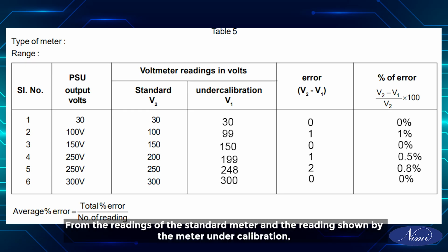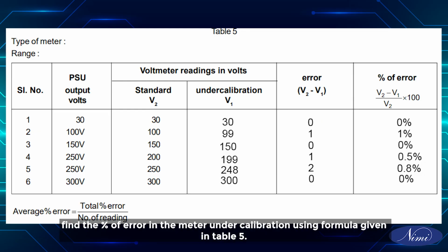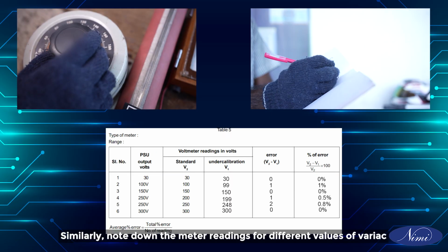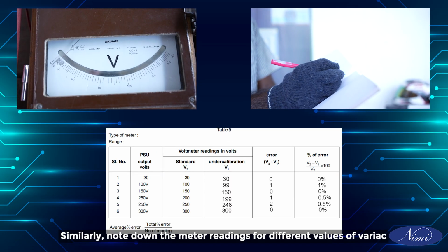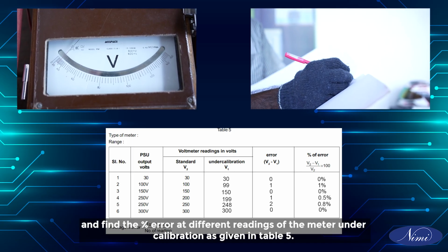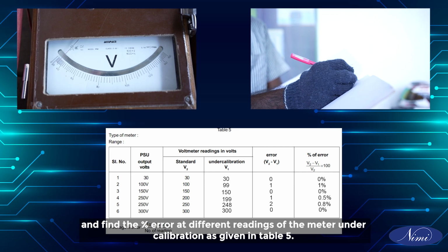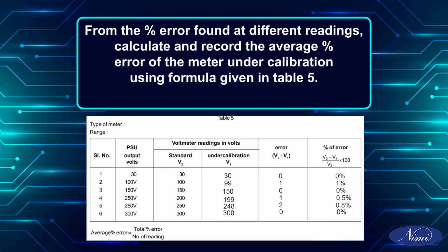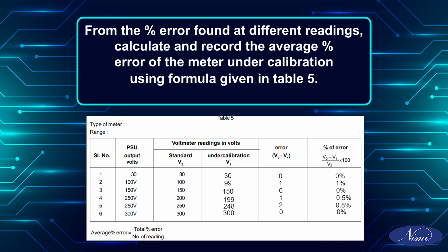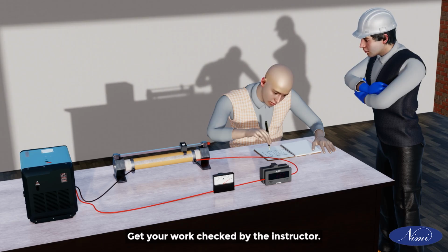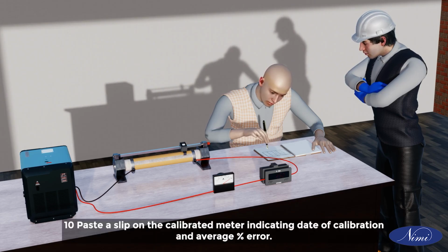From the readings of the standard meter and the reading shown by the meter under calibration, find the percent of error in the meter under calibration using formula given in table 5. Similarly, note down the meter readings for different values of variac and find the percentage error at different readings of the meter under calibration as given in table 5. From the percentage error found at different readings, calculate and record the average percentage error of the meter under calibration using formula given in table 5. Get your work checked by the instructor. Paste a slip on the calibrated meter indicating date of calibration and average percentage error.